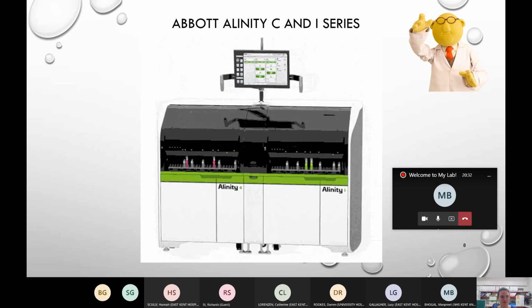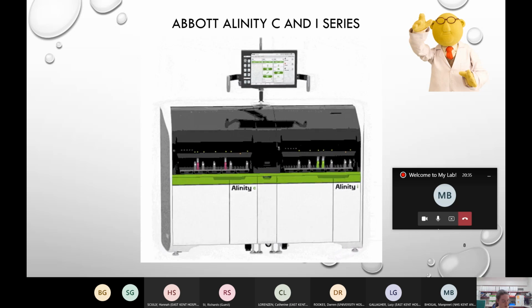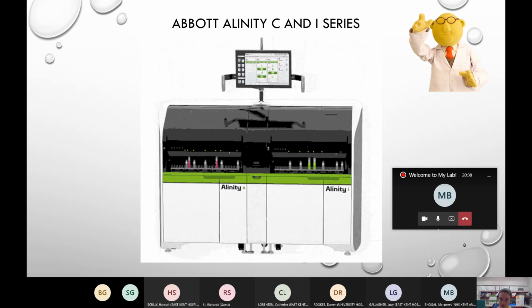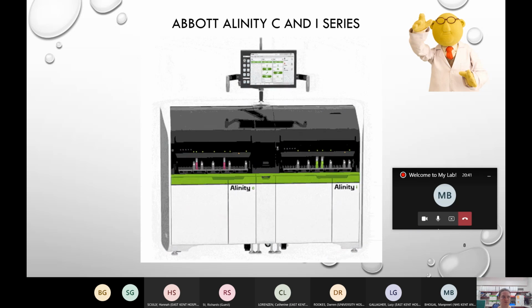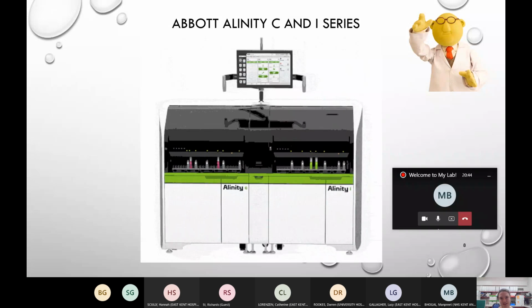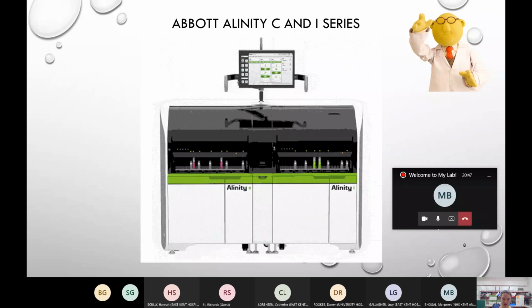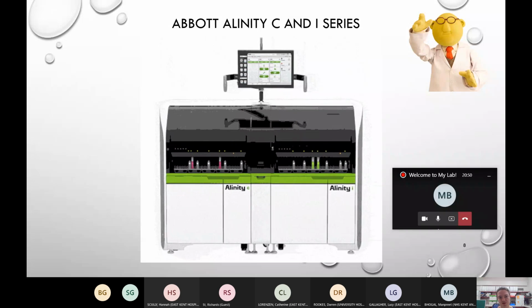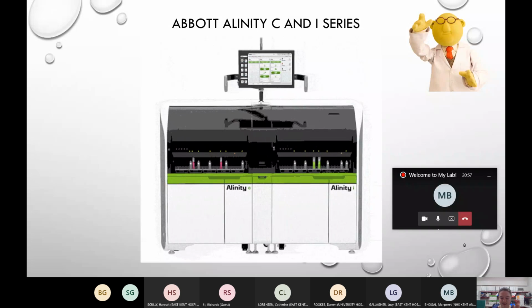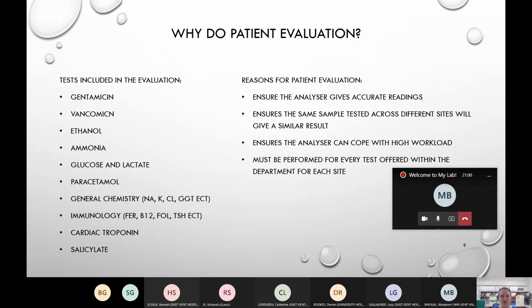So yeah, this is our new analyzer that we've had within the lab for the past, I think, couple of months. At the moment, it's not currently in use because we are doing what's called patient evaluation, and we're testing this analyzer to make sure that it produces results that would be suitable for use within the hospital or for our GP work that we do within our trust. So to give a breakdown, what is patient evaluation and why do it? Patient evaluation is basically just making sure that the analyzer is producing the correct results. And we need to make sure that we have known values to compare this analyzer to.